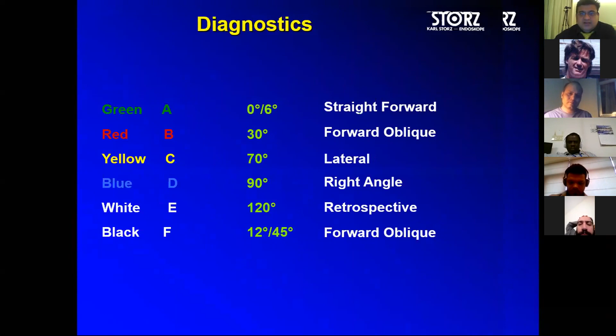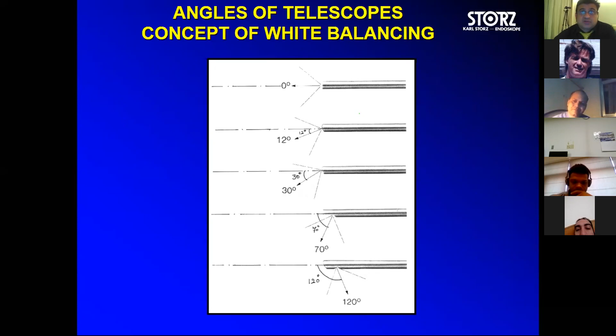But when we have a 30-degree angle of view, the last rod lens is actually cut at an angle of 30 degrees with respect to the zero horizontal axis. In 70 degree, it is cut at that angle so that you can see laterally. That is why I was telling, when you are changing from 0 to 45 and 70, you need not do a white balancing, and we can save a lot of anesthesia time, because white balancing color temperature is dependent on the color temperature of the light source, which is usually a xenon light source nowadays.